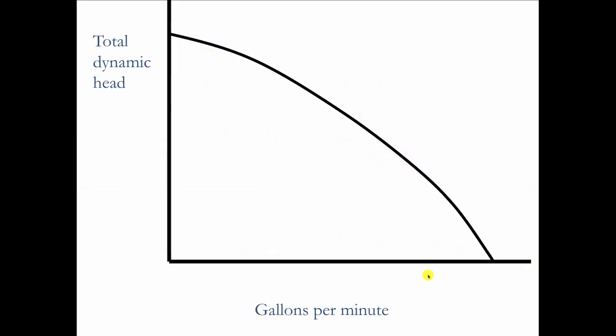If we wanted to know how much water was flowing with this circulator, we would go on the manufacturer's pump performance curve showing the gallons per minute against total dynamic head, which has nothing to do with the height of the building. This has to do with the resistance to flow as the water moves through the pipe. As the resistance gets lower, the flow rate will go higher. If we begin to close valves, that increases the resistance, and the gallons per minute flowing will slow down. So GPM versus resistance to flow. As we throttle down on a circulator, it builds pressure.